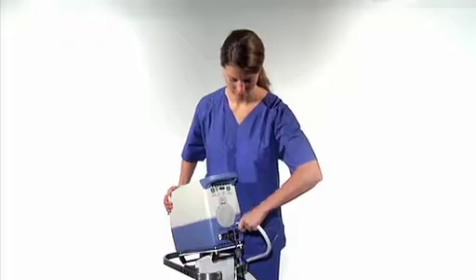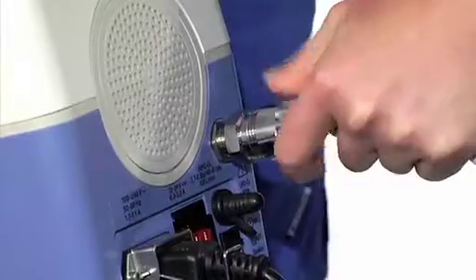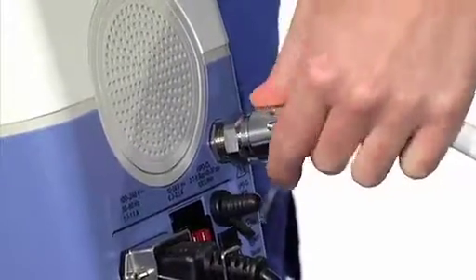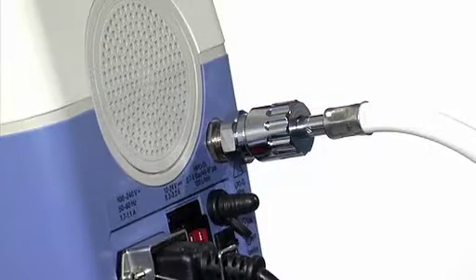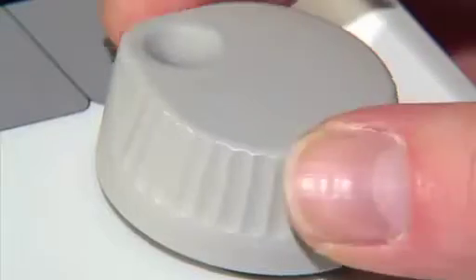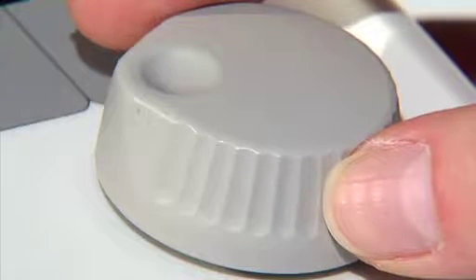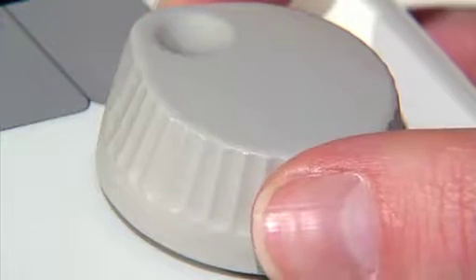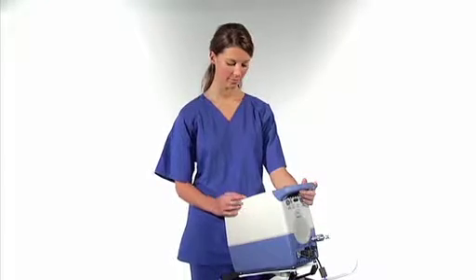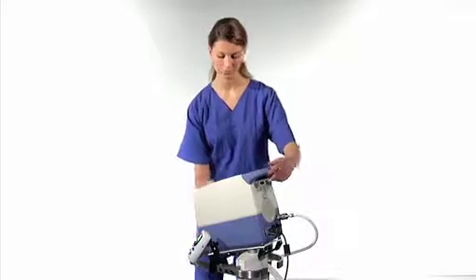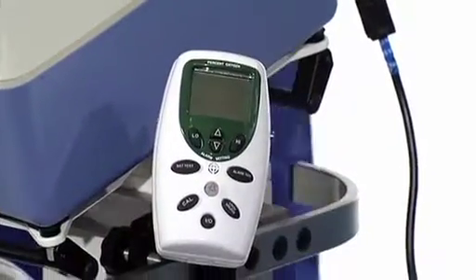Please screw the oxygen compressed gas hose onto the high-pressure oxygen connector. Using a high-pressure oxygen source, you can set the FiO2 concentration directly on the device. Please remember that Carina does not regulate the delivered oxygen concentration. Because of this, we recommend using an external oxygen monitor.